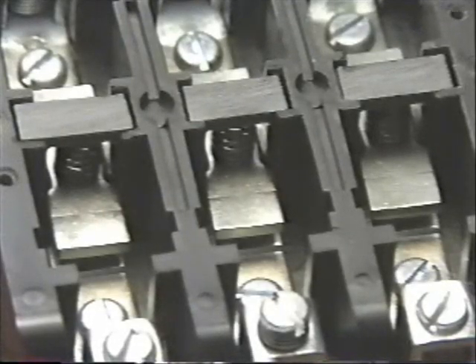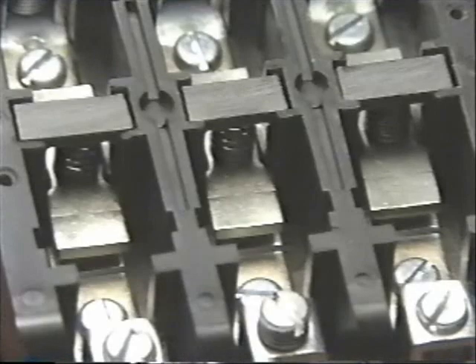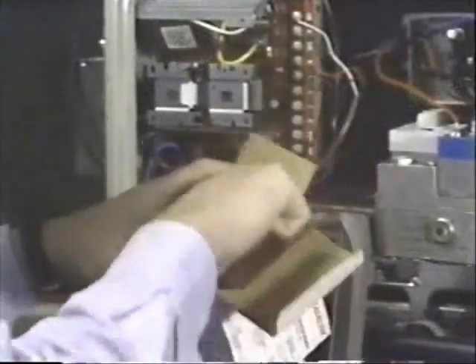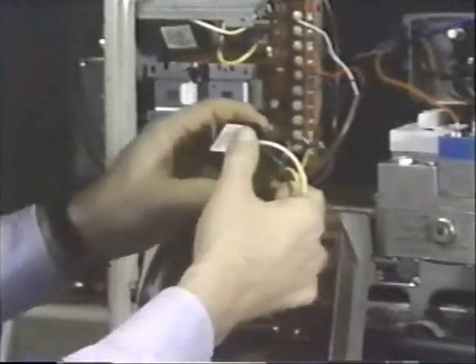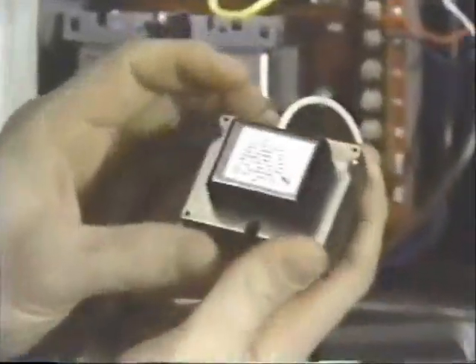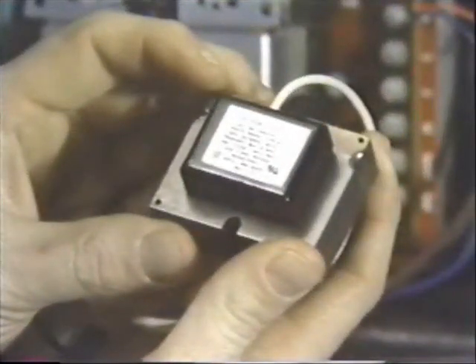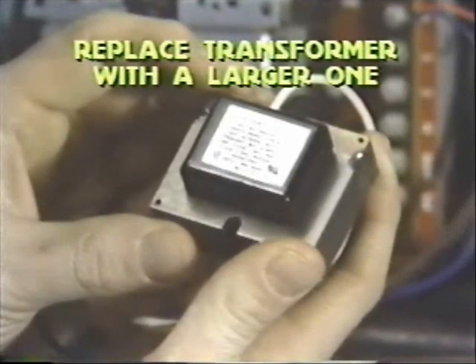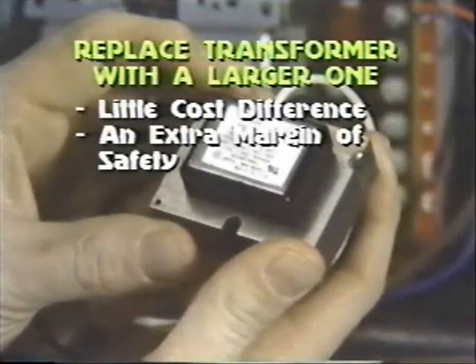They in turn can cause faulty operation of the compressor motor. So selecting transformers of adequate size is very important to the performance and lifespan of electrical components in air conditioning systems. For service work, there are two useful rules of thumb which will help you choose the right size transformer. It's usually a good idea to replace a burned out transformer with a bigger one. The cost difference is negligible, and the larger size gives you an extra margin of safety.